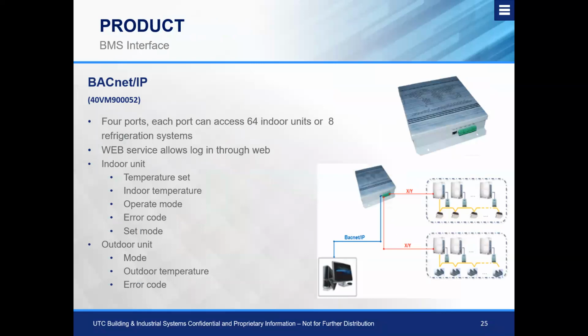As we get into upper level control through the BACnet over IP interface, essentially this converts that Carrier VRF protocol over into BACnet protocol, and also has a built-in centralized controller access via LAN cable, by typing the device's IP address into an internet browser, and you're able to see all of our indoor units. When we integrate, we get our indoor unit information such as temperature set point, indoor temperature, operating mode, and air flow, depending on the mode that we want to set. And with the outdoor unit, we get the mode, the outdoor temperature, and air flow. We have 4 ports available on this device. Each port can access 64 indoor units or 8 refrigeration systems.